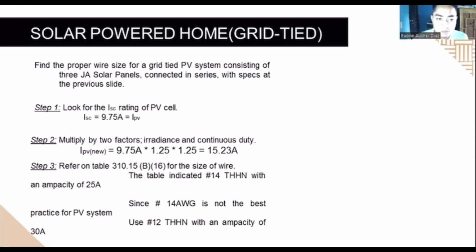Find the proper wire size for a grid-tied PV system, consisting of three JA Solar Panels connected in series with the specs at the previous slide. The JA Solar Panels are half-cut cell panels, a technology that increases their energy output. Step 1. Look for the ISC rating of the PV cell. Short circuit current is equal to 9.75 amps.